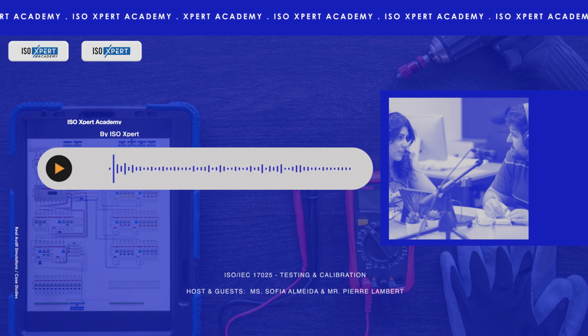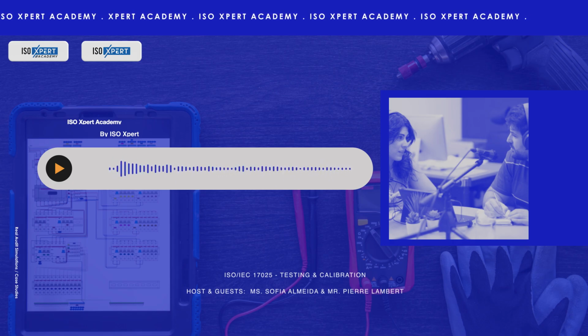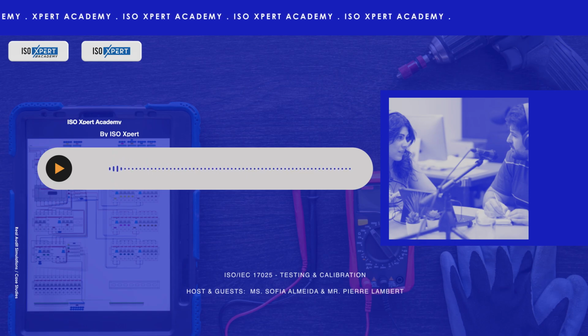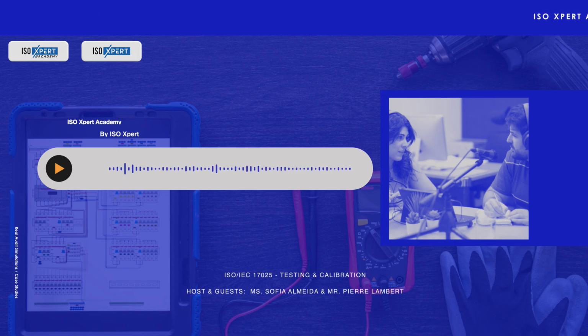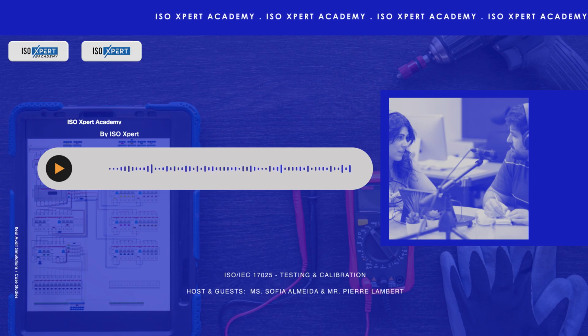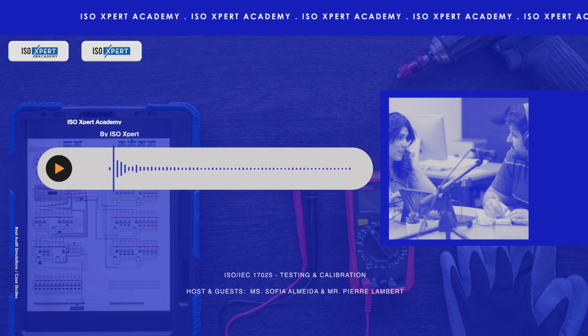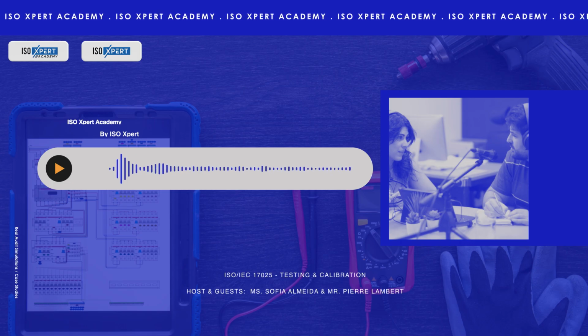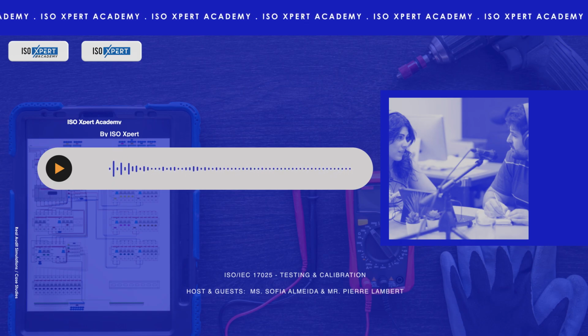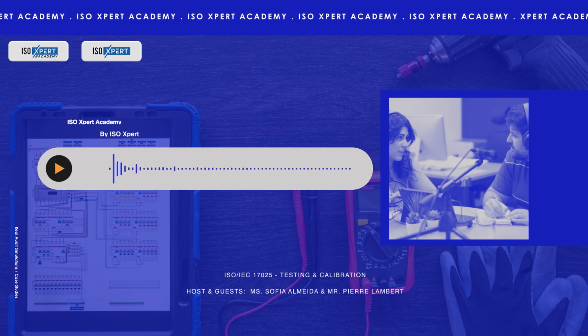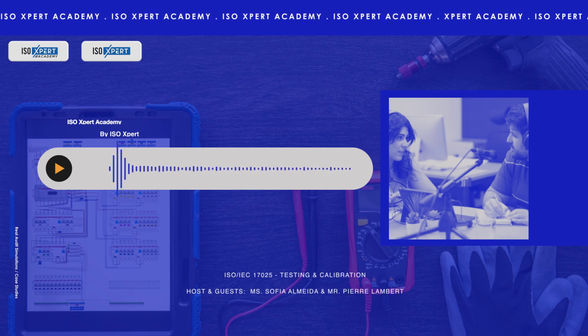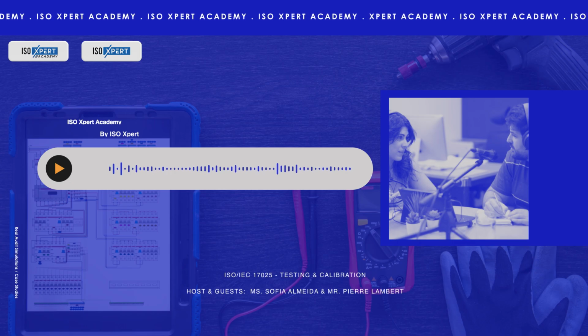Exactly. And beyond just fixing the specific NCRs, the audit team also gave some broader strategic recommendations. Like what? Things like maintain regular competence reviews, especially when people are new or methods change, really embedding that culture of documented competence, reinforcing NCR 1. Yep. Also setting up automated reminders for calibration and maintenance to avoid things like that missed oven check in NCR 2. Makes sense. Use technology. And crucially, strengthen those method validation procedures. Do it before using new methods on customer jobs, not after the fact. Address NCR 3 head-on. Get it right from the start. And finally, leverage data analytics for internal QC. Turn those checks into real insights, as suggested by OBS 3.